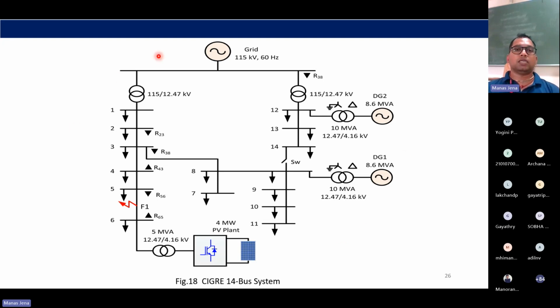So, what he did was build this 14 bus system and connect a 4 megawatt IBR to bus 6, okay. And the relays under consideration are R65 and R56. If you look at R56, if a fault happens on this line, R56 is actually seeing the response from the conventional grid. So, the response that the R56 relay will see to this fault is being fed by the conventional resources, whereas whatever R65 will see is the response of the inverter, okay.